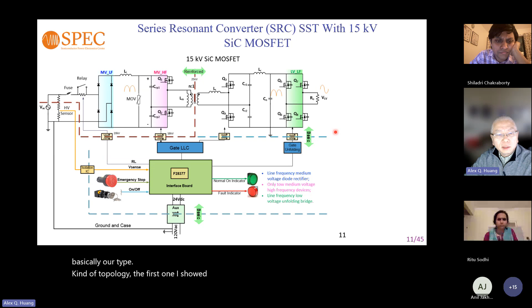Since it's a resonant converter, it will copy the half sine to the low voltage side. So this is 7.2 kV, and this is a couple hundred volts. Then you can use another low voltage silicon device to get a full sine wave. So this is basically a type A kind of topology - the first one I showed, classified as type A solid state transformer.